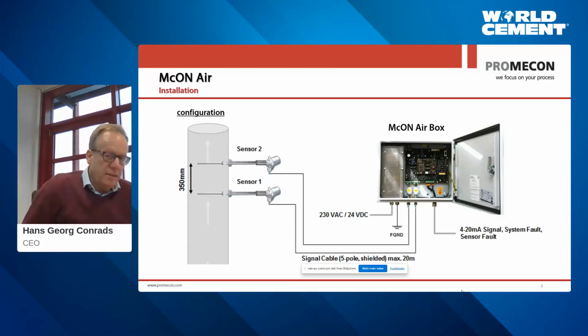That's pretty much it, because there's not much that you have to do in order to check plausibility on drift or on zero. You know, for example, we don't have any zero. If you have a delta P measurement, you always have a 0 point that you need to check for drift. Now, what's the time of flight between sensor 1 and sensor 2 if the velocity is 0?